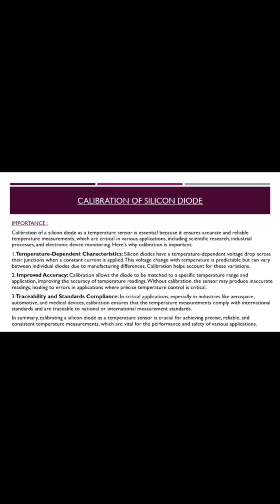Second one is improved accuracy. Calibration allows the diode to be matched to a specific temperature range and application, improving the accuracy of temperature readings. Without calibration, the sensor may produce inaccurate readings, leading to errors in applications where precise temperature control is critical. Third one is traceability and standards compliance. In critical applications, especially in industries like aerospace, automotive, and medical devices, calibration ensures that temperature measurements comply with international standards and are traceable to national or international measurement standards.